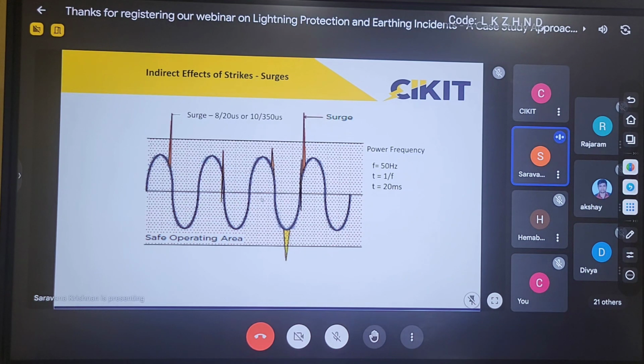Since the duration is very short, we have to provide separate devices. The MCB operates only after 3 to 5 cycles; there is a definite time interval. It is not an instantaneous device. So MCBs and fuses won't operate, and they won't be able to sense the surges. That is the reason you go for a separate device, the surge protection device.